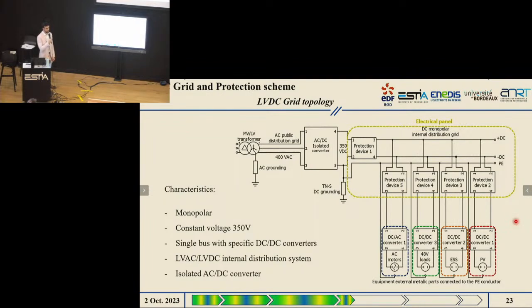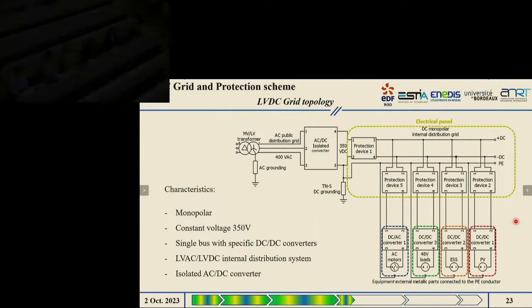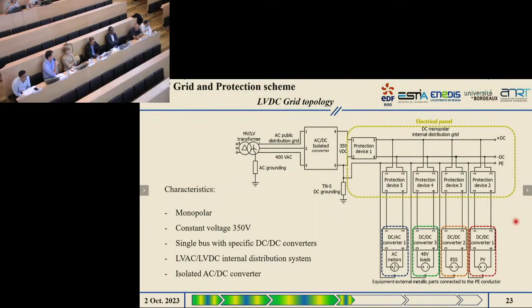Okay, so if you need isolation at the converter, then that's good, because at the same time you can gain what you call the active short circuit capability, the fact that you can limit and open the circuit at the converter level, so it solves two problems. So if this is a clear requirement that you need to disconnect low voltage AC from low voltage DC, then write it clearly, and you can more easily discard other topologies, as discussed before. Agreed.